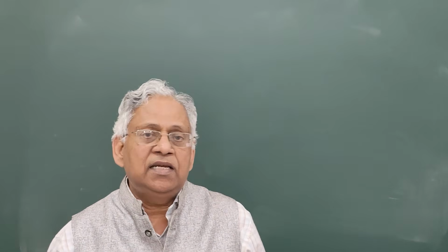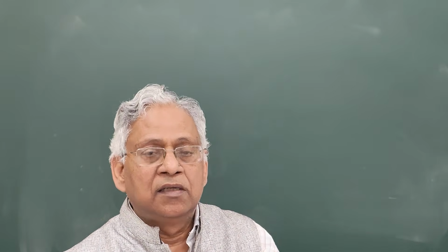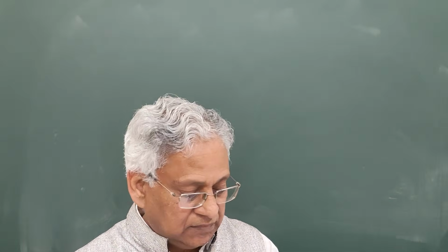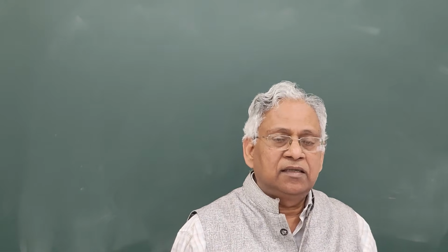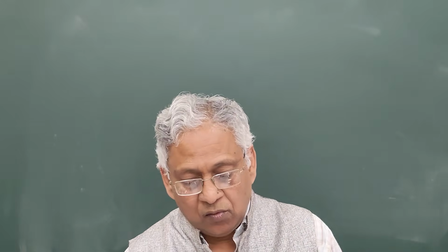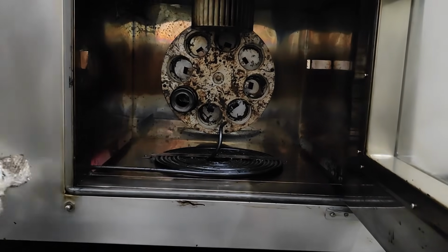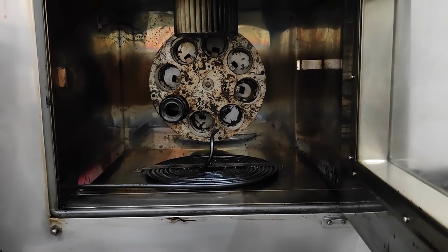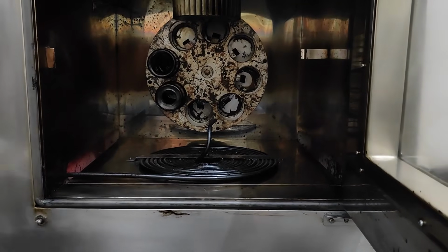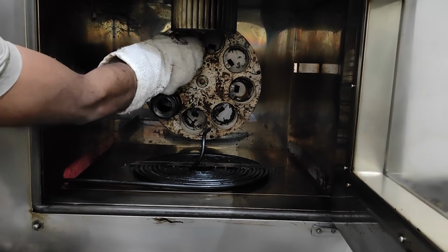After cooling, take the weight of each glass container using the analytical balance with the accuracy of 0.001 grams. Now set the oven at test temperature and set the airflow at 4000 ml per minute. Arrange these containers in the carriage so that the carriage is balanced. Any empty space should be filled with unused containers, meaning all holes of this carriage should be filled.